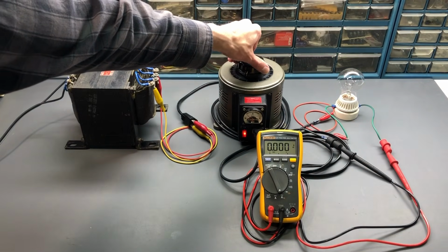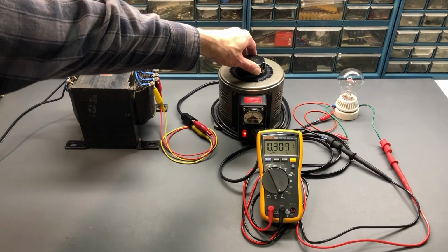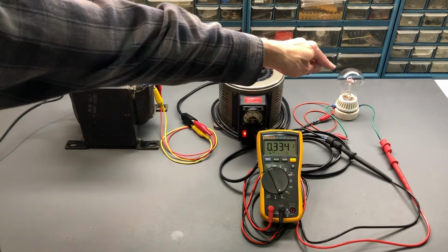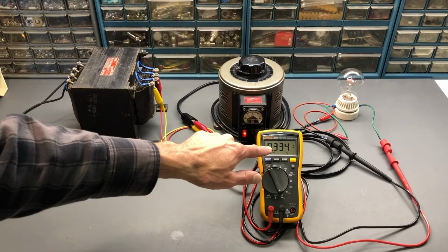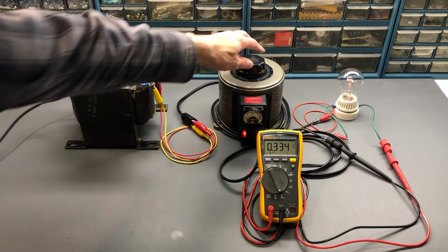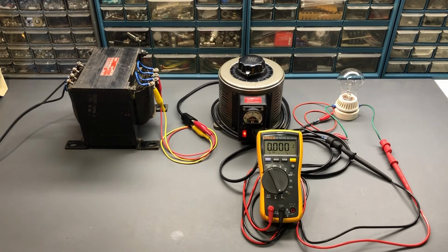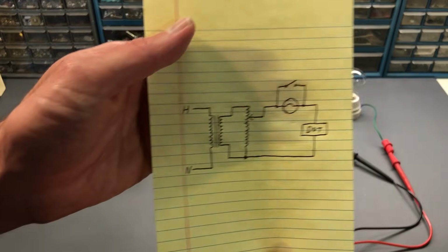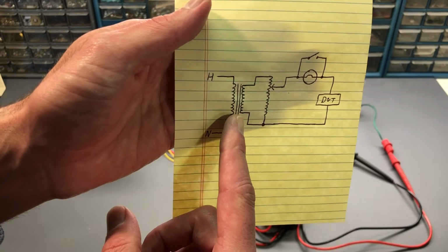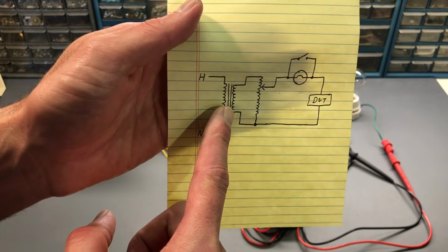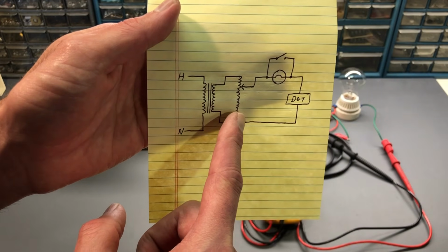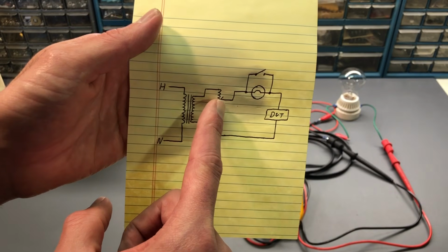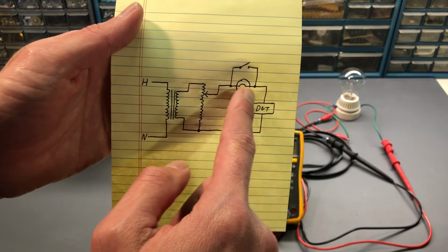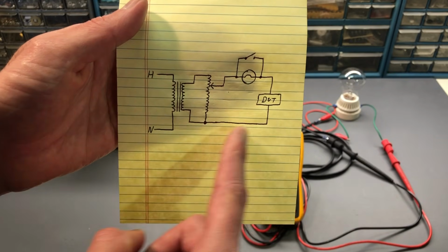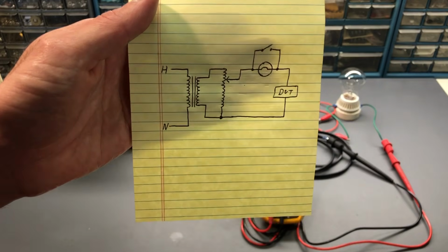When you start the Variac out down in this low range, there's no jumping up of current, no spikes in the current, very slight voltage, just a little bit of a glow there, very low current flow, just about 1/3 of an amp right there. So again, this arrangement works very, very well. There are two things about this arrangement that I like. One of them is that you have complete isolation in the components after the isolation transformer. So your AC line is applied to the transformer, and then even your Variac is isolated in this configuration. That's a nice safety feature. And then, of course, the device you're testing is also isolated, as well as the bulb. So everything that you're working on or coming in contact with over here, you do have isolation. So again, that's a nice bonus to this.